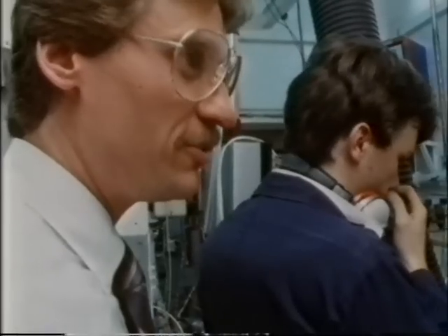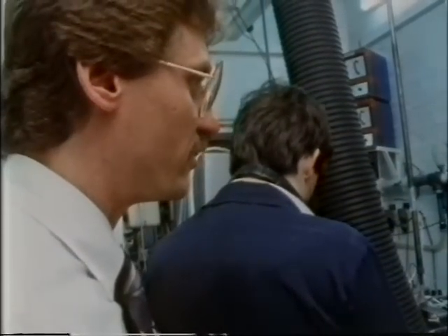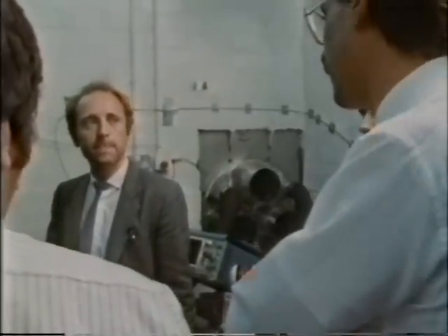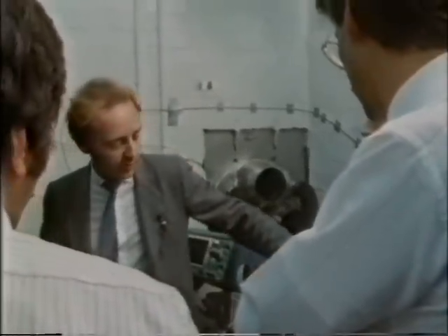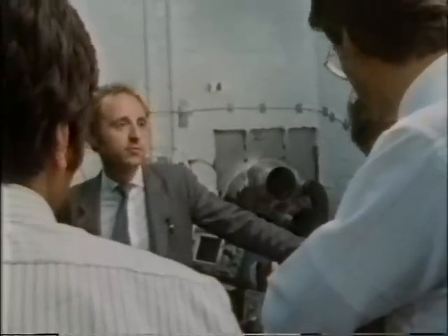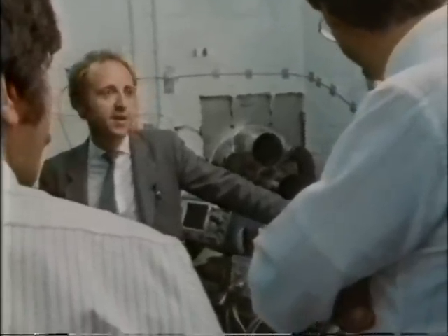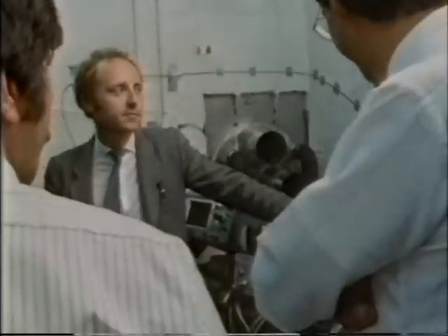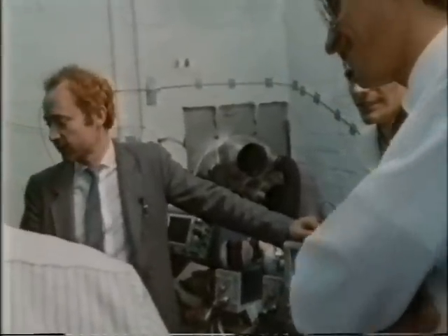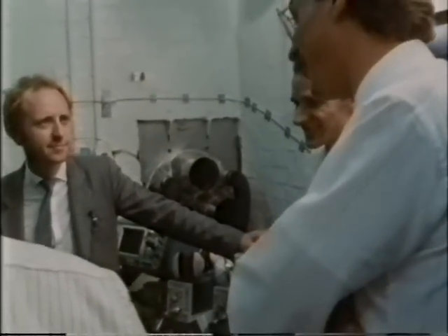Do you think it's time to change the cam sensor finger so we can maybe get a little of that noise out of it, if there is any there? Noise is jargon for the unwanted electromagnetic pulses. Yeah, we're still seeing noise, and the strategy is obviously going into some high region, and the fuel shutoff that's been put in for protection is catching it. It really is shutting it off like it's supposed to. So the strategy is working okay. The good news is the engine runs, but the bad news is not all the time.